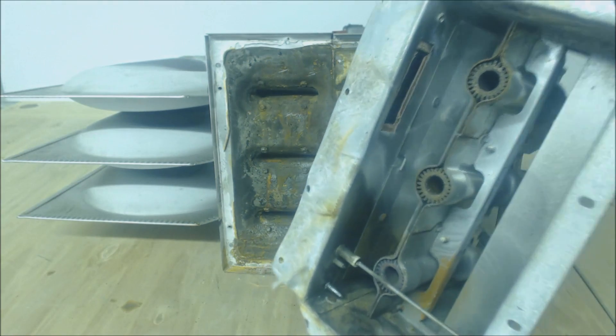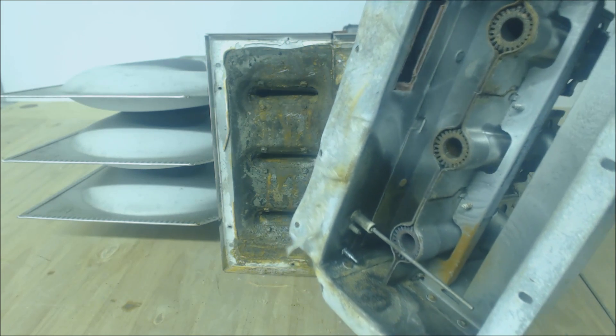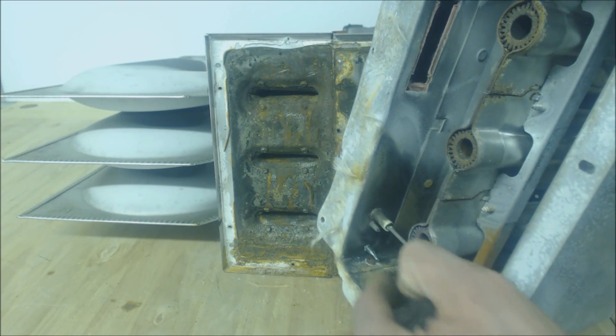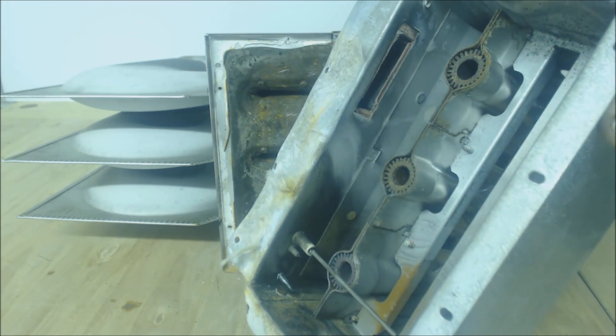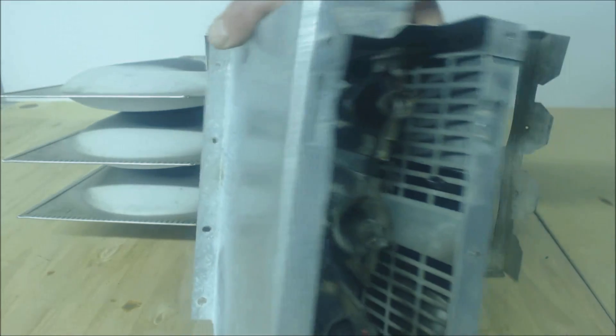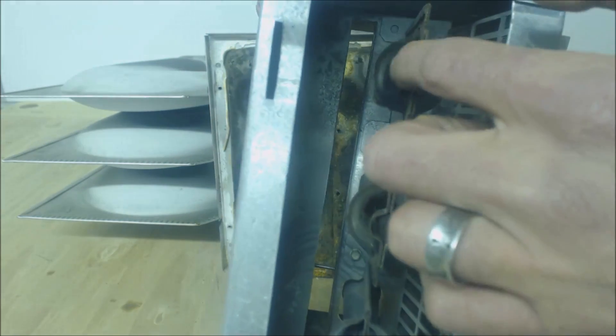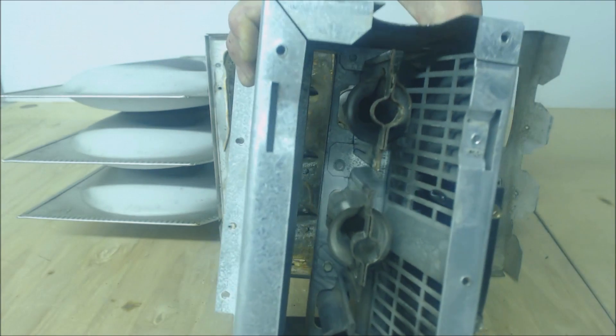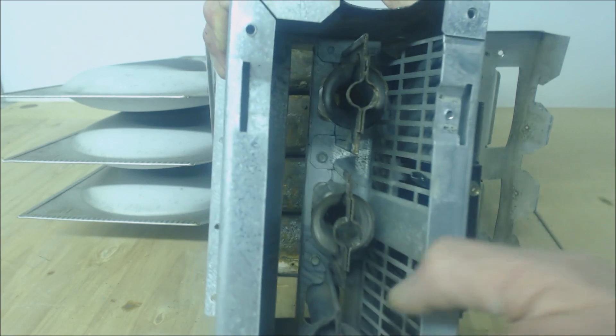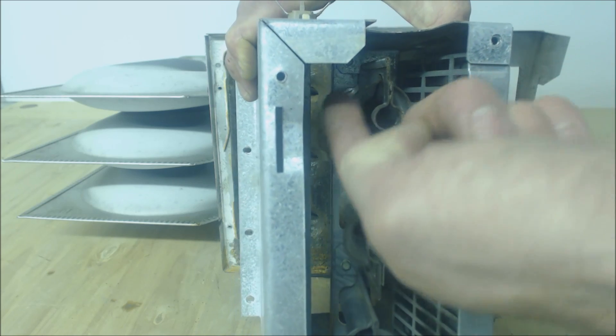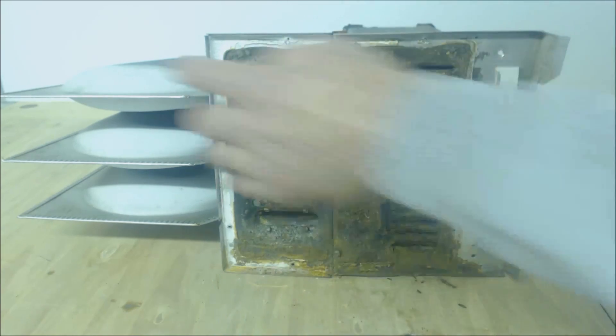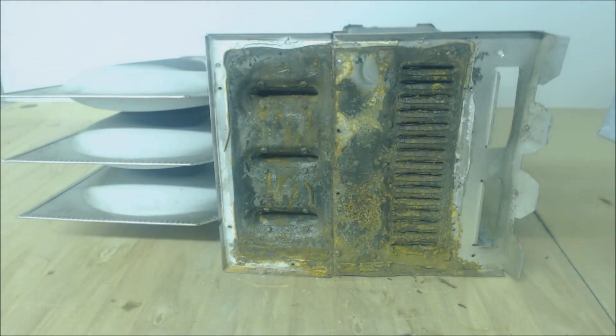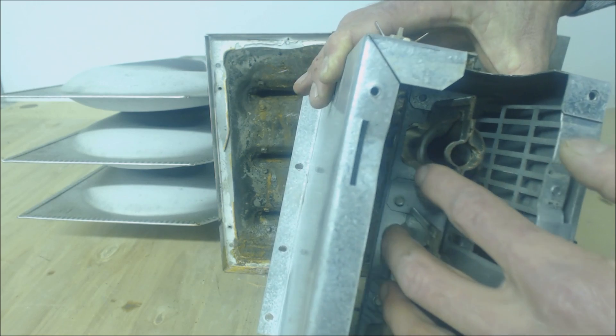Some of the things you want to look out for when doing preventative maintenance for gas furnaces, especially these older early 90s furnaces: you want to look in this area for any excess soot build-up. You want to make sure that you see a flame from this side. You want to see that the flame on each of these three are all getting pulled in basically in the same manner. You don't want to see one here getting pulled nice and straight and this one is off a little bit. You could have a cracked heat exchanger, say a crack over in here somewhere.